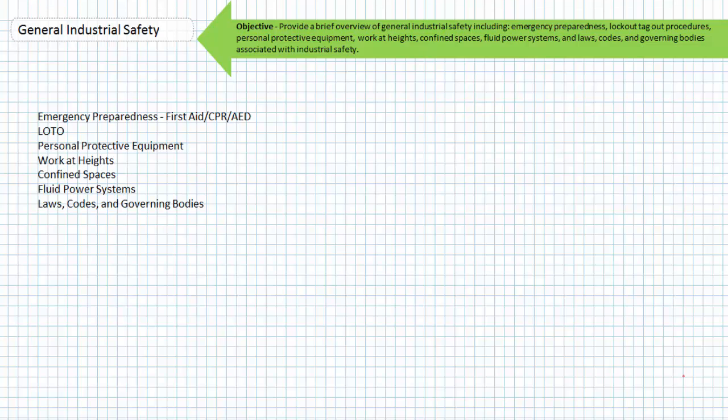Consider other forms of hazardous energy, including but not limited to thermal, hydraulic pressure, stored hydraulic pressure in an accumulator, stored electrical energy in batteries or components like capacitors, chemical energy, or suspended weights. All these forms of hazardous energy need to be locked out, blocked, or released.